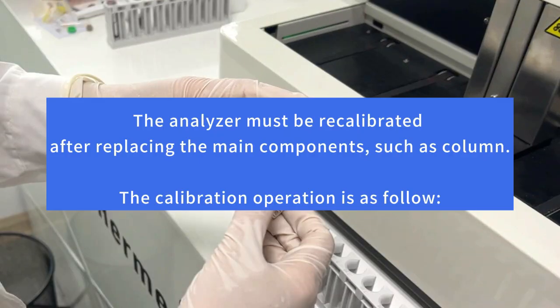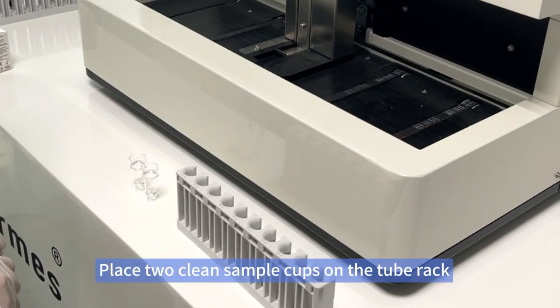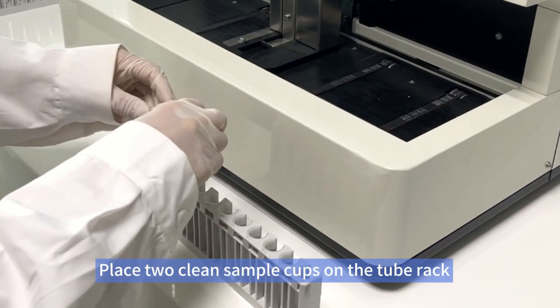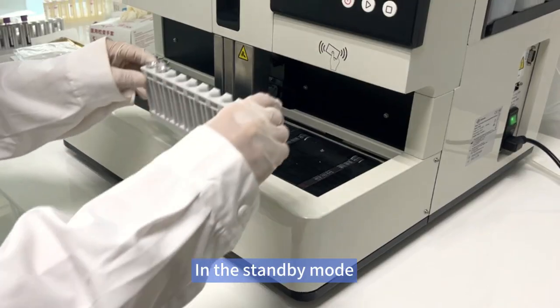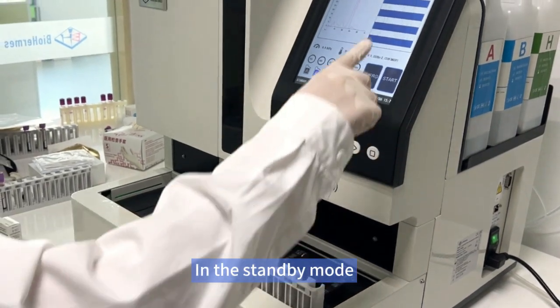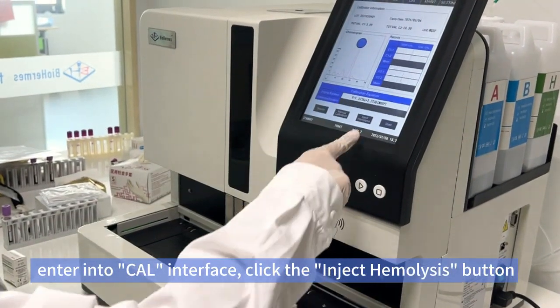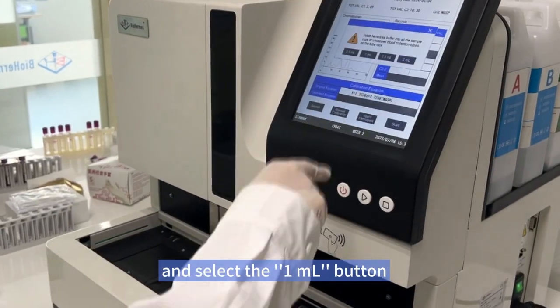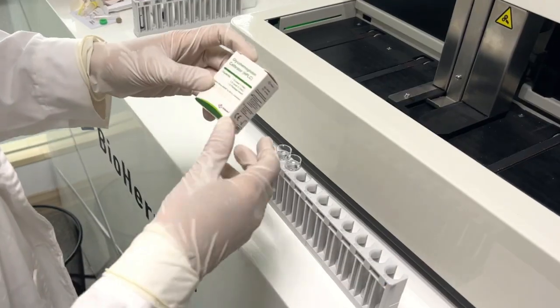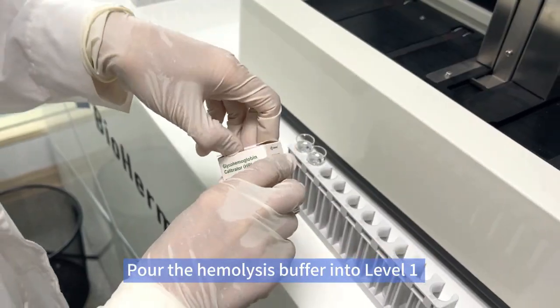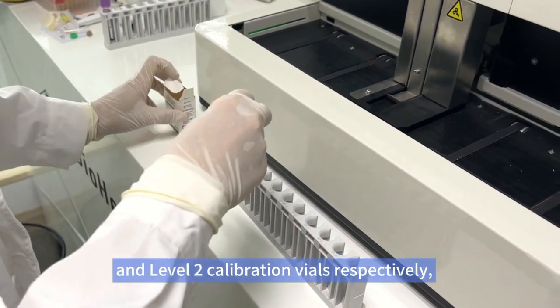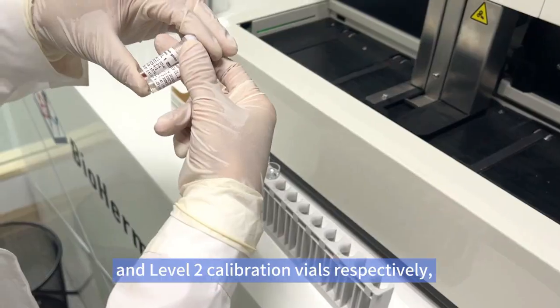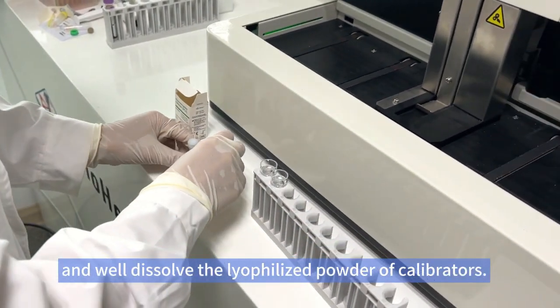Calibration. The analyzer must be recalibrated after replacing the main components, such as the column. The calibration operation is as follows. Place 2 clean sample cups on the tube rack, and then place the tube rack in the sample loader. In the standby mode, enter into a cal interface, click the Inject Hemolysis button and select the 1 ml button. Pour the hemolysis buffer into level 1 and level 2 calibration vials respectively, and well dissolve the lyophilized powder of calibrators.